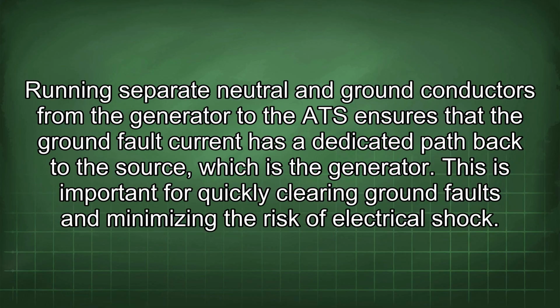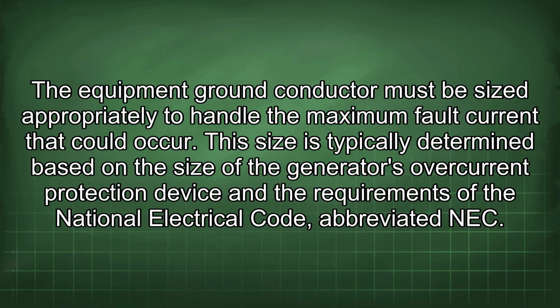Running separate neutral and ground conductors from the generator to the ATS ensures that the ground fault current has a dedicated path back to the source, which is the generator. This is important for quickly clearing ground faults and minimizing the risk of electrical shock. The equipment ground conductor must be sized appropriately to handle the maximum fault current that could occur. This size is typically determined based on the size of the generator's overcurrent protection device and the requirements of the National Electrical Code, abbreviated NEC.